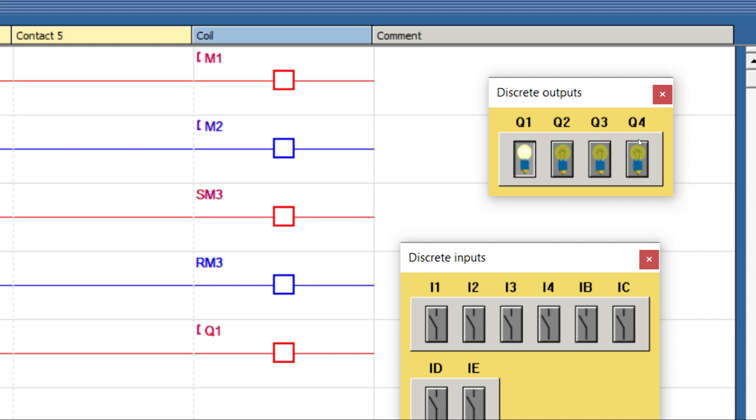This is how you can maintain your pressure in pipeline with digital outputs - that means any DOL starter or star delta starter - using a pressure transducer with input of 0 to 10 volt. This 0 to 10 volt you can use with any range of 0 to 16 bar, 0 to 20 bar, but you have to calculate the bar value between 0 to 10 volt.